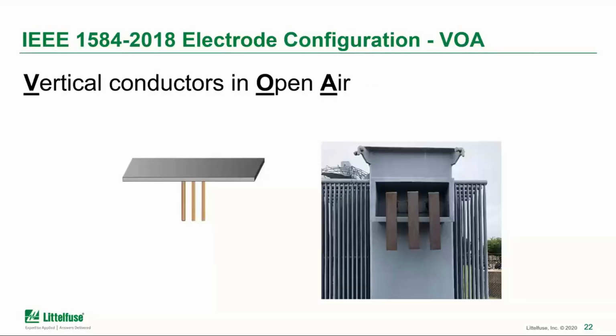And the next, the last two here, the VOA configuration, the vertical conductors in open air. The photo on the right shows the bus bar in open air and how they're positioned downward, in a vertical fashion there. And again, seeing what was on the last few slides, it's no surprise that the arc energy is directed down off the ends of those bus bar.